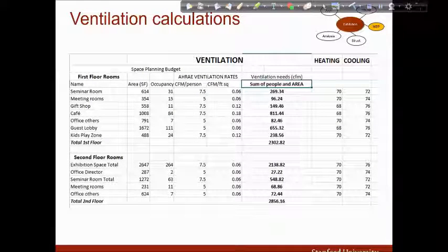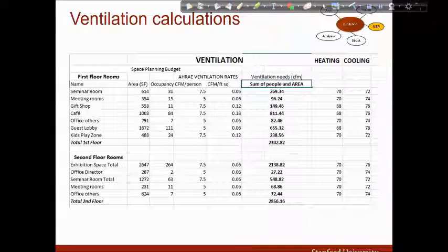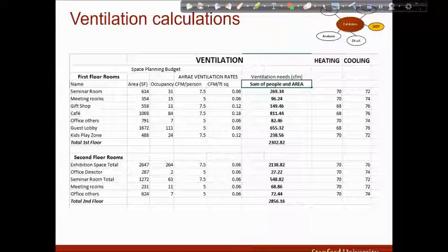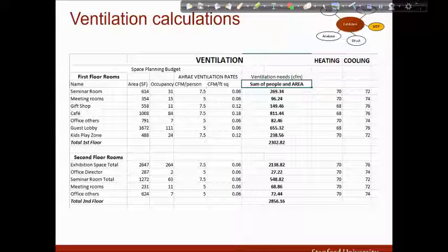In my architectural design I focused on creating a shape that will maximize natural ventilation. Most rooms are equipped with ceiling fans to circulate air. As a result I will be able to meet the ventilation needs for most days of the year. However, there will be a few days in which I will not be able to meet them with natural flushing and ceiling fans, so I am adding Heat Recovery Ventilators, HRVs, which will operate on those days. HRVs transfer some of the heat and moisture between the incoming and outgoing air making them much more energy efficient. I added 3 HRVs on the first floor and 2 HRVs on the second floor, with 2 placed in the MEP room and the others above the ceiling in the zones they cover. I calculated the ventilation needs as shown in the spreadsheet with the calculations.